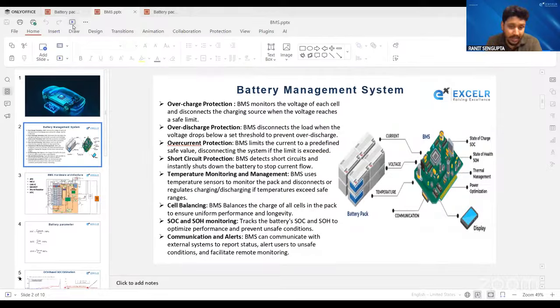Because whenever we increase this tolerance, it will give faulty data. After suppose 100 cycles, it may become imbalanced, as you've seen. So best practice is to keep a very low tolerance, 0.1 to 0.5%. Otherwise your battery will malfunction.